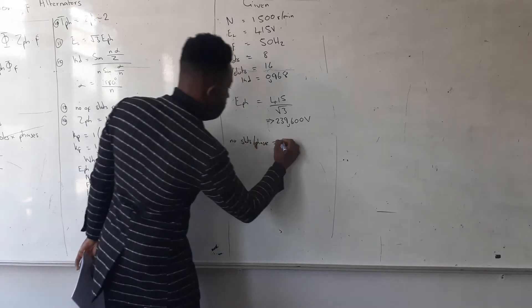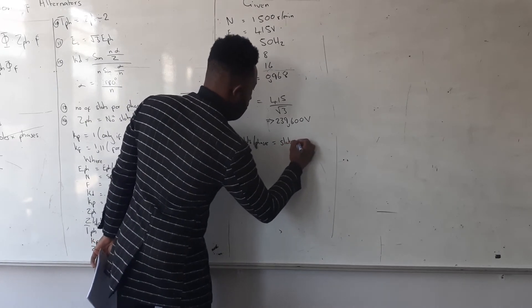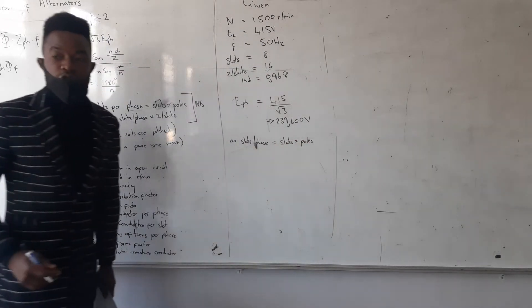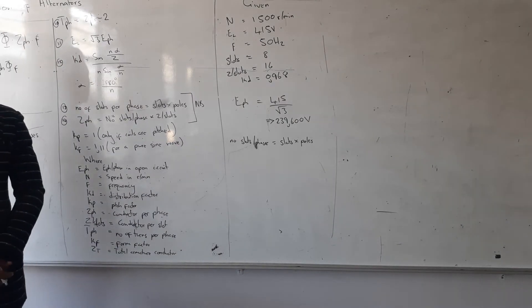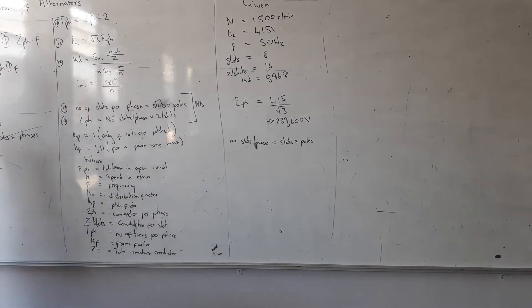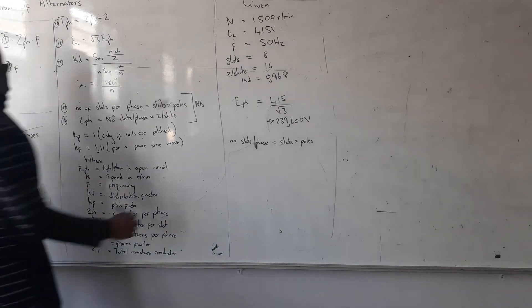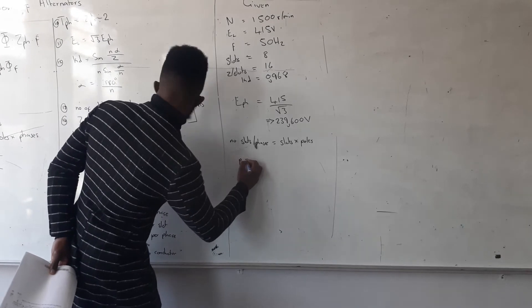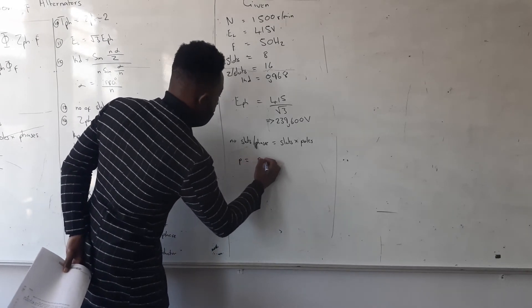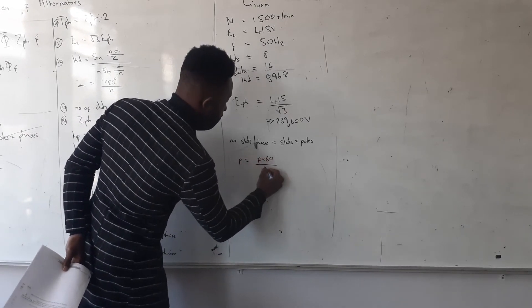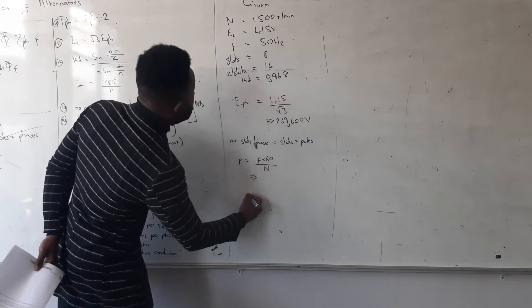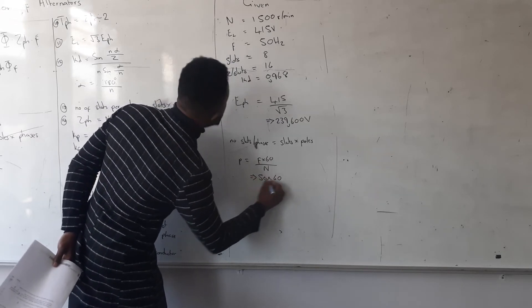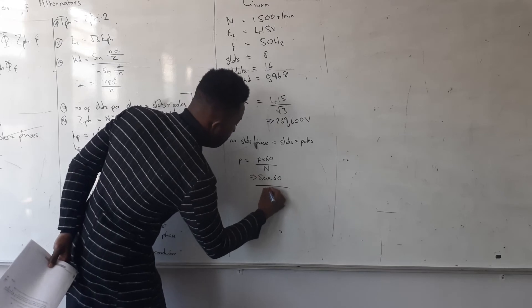Number of slots per phase is equal to slots divided by poles. Now, I don't have the number of poles, so I have to calculate using which formula? The formula of the frequency. So here it's going to be what? To get my P, it's going to be F times 60 divided by N. What is my frequency? It's 50 times 60 divided by the speed of 1500.